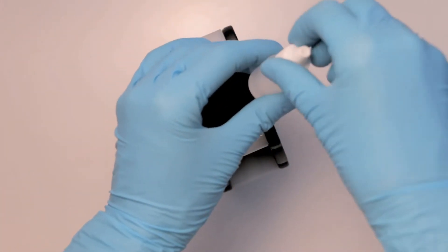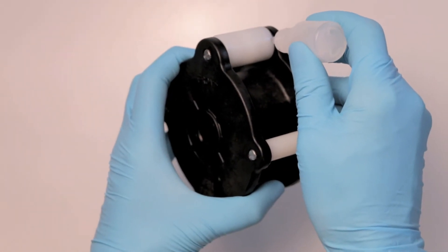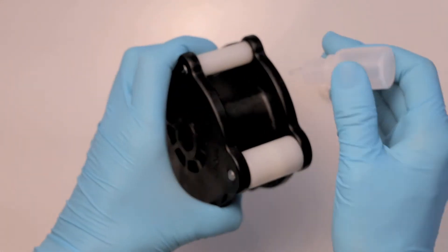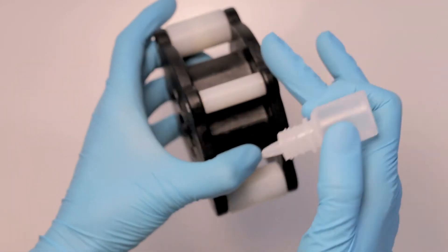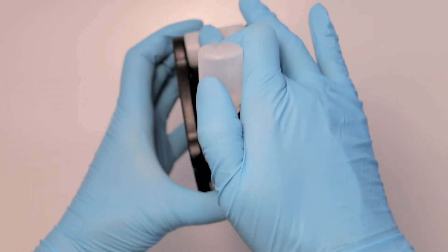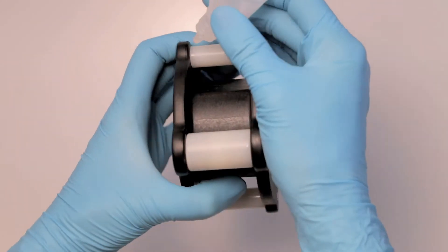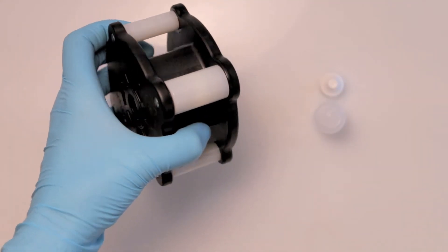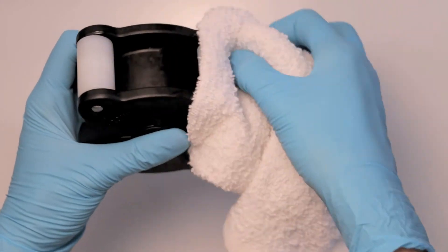The roller assembly is made of two squeeze rollers and two guide rollers. The larger squeeze rollers contain bearings. Place a drop of silicone oil at the end of the rollers to lubricate these bearings. It's also a good idea to lubricate the guide rollers too, making sure they're free spinning. Clean off any excess oil that may have ended up on the surface of the rollers themselves. Tube assemblies and silicone oil don't mix.